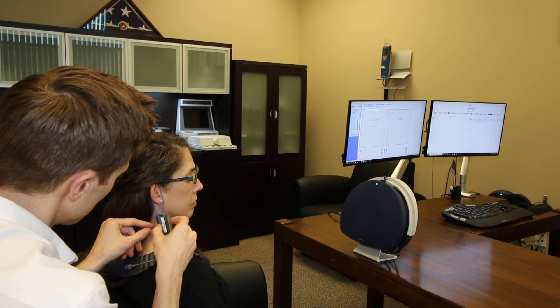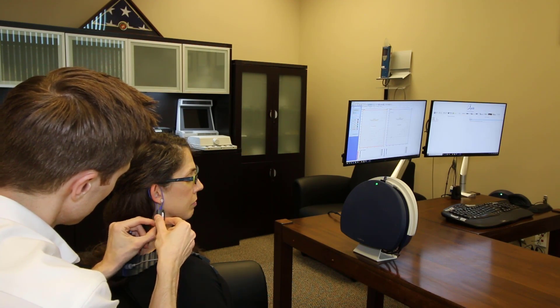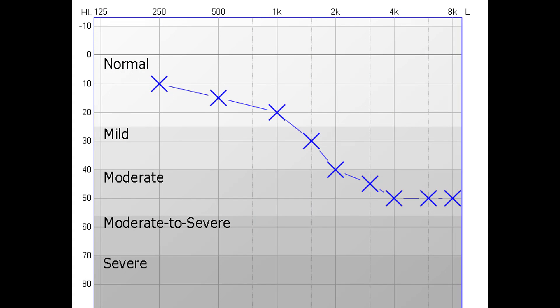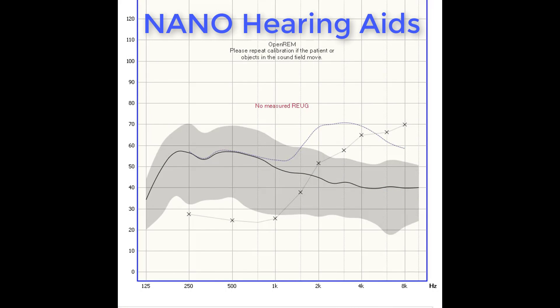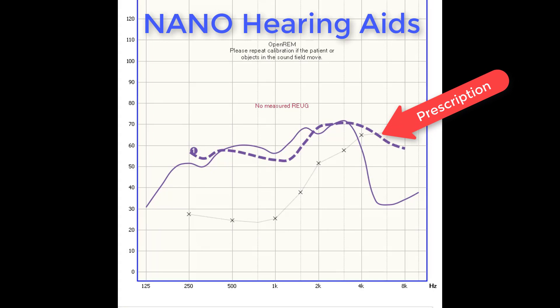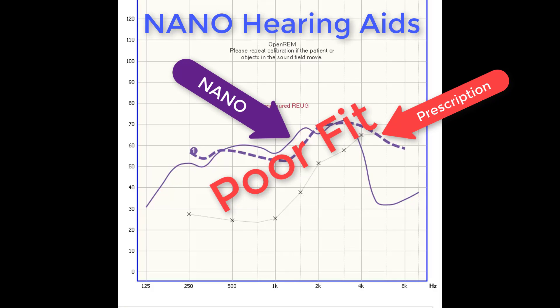Next, I set up the Otometrics Aurical probe microphone measurement equipment to perform real ear measurement with both devices to measure how they perform inside of an actual user's ear canal. This will also allow us to see if these devices are capable of matching the prescription for a normal sloping to moderate sensorineural hearing loss, which is a very easy type of hearing loss prescription to match. As we run through the test sequence, we can see that the Nano hearing aids, when set to their lowest volume level, are providing amplification indicated by the solid purple line. The prescriptive targets, indicated by the hash mark line, are not being matched by the output of the Nano hearing aid, which would indicate a poor fit for this individual and their hearing loss.